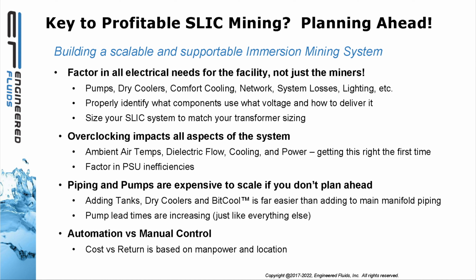Pump lead times are increasing dramatically as well. Again, we've solved the problem on the dry cooler, getting that back down to about 14 weeks. But for pumps, we're starting to see those stretch out as well, particularly large ones in the 25, 30, 40, and 50 horsepower for very large systems. The smaller pumps are actually a lot easier to find, we don't see a problem there. But definitely on the larger pumps, it always pays to plan ahead.